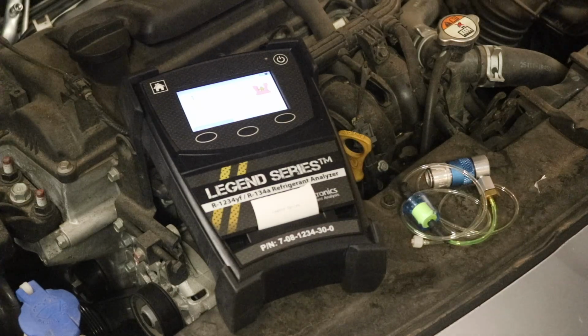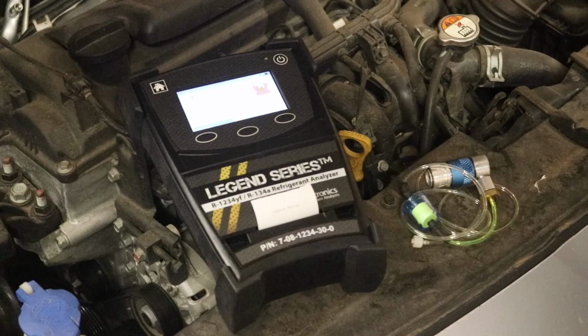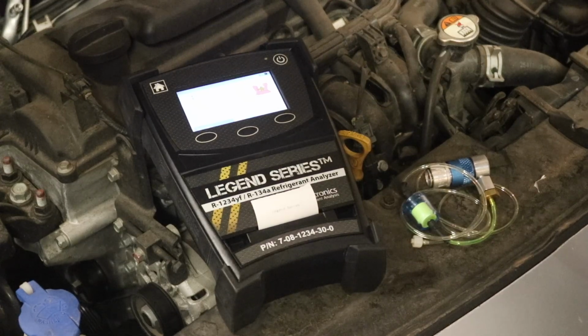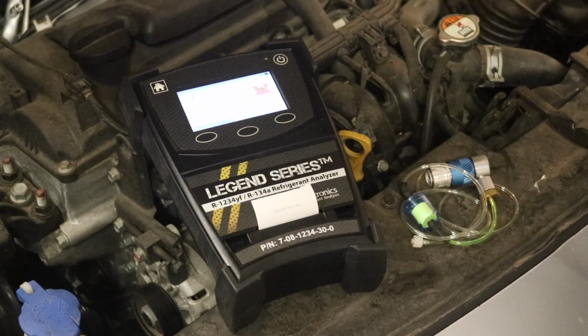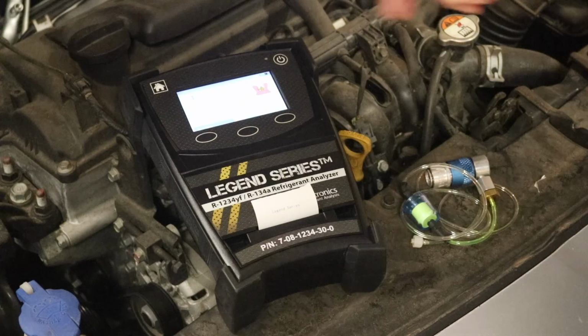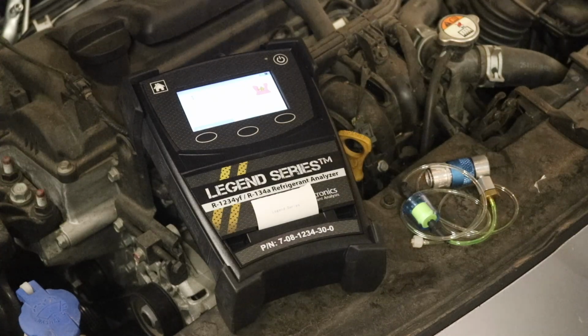This particular machine is capable of analysing R12, R134A, R1234YF, also detecting flammable refrigerants such as hydrocarbons and determining the amount of air content that might be in the system, which can be linked to high moisture content. So in this particular case, I'm going to select R134A because we believe that's what this system should contain.